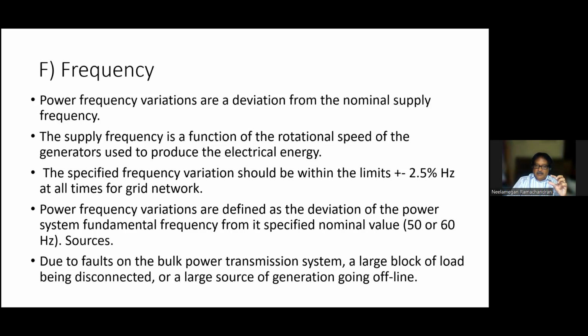So we are maintaining that frequency, but occasionally we get this problem in areas like the mesh belt furnace, whereby suddenly that furnace is switched off or something trips in the furnace where the bulk load is, and a slight fluctuation is there. This can be sensed when a small motor, a spindle motor, is connected with a variable frequency drive. If it is connected in that line and this major load is suddenly switched off, there will be a minor disturbance in the frequency which will affect the quality of the product.